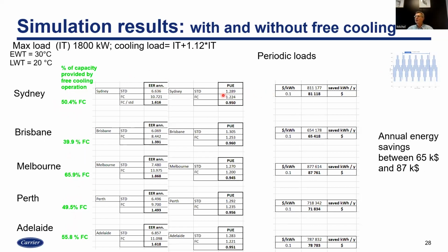Then I calculated standard meaning without free cooling, and FC meaning free cooling operation, for different locations. I'm calculating EER, the efficiency from the chiller perspective, and PUE, the power usage effectiveness, which is the value used by our colleagues in data centers. Higher EER is better, and lower PUE is better. A good PUE is around 1.2, not so good is 1.4. To make a long story short, I see a positive impact from free cooling operation.